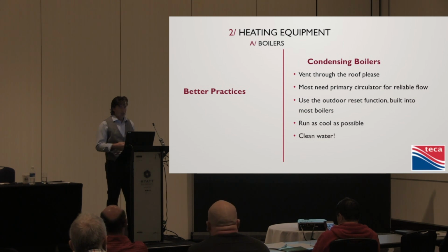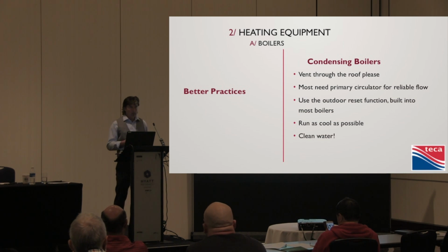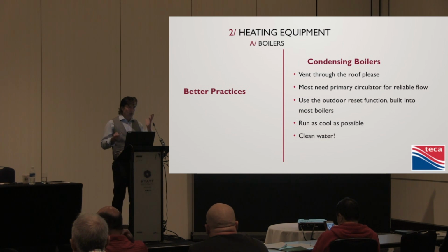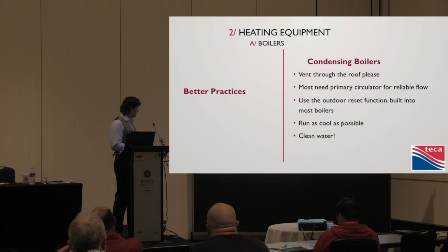Use clean water. I said it's low mass. The boiler is low mass. They're very fine in the heat exchanger and stainless steel. Don't just have miles of radiant pipe and nobody put a cap on it, and hook it all up and then just run this water through with a bunch of gunk and whatever you filled the system with, because it's going to clog up that thing. It's not like the old cast iron boiler that could take anything going through there. These are very particular to nice clean water going through them.